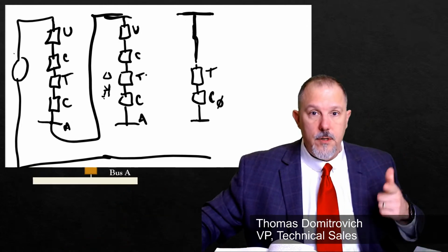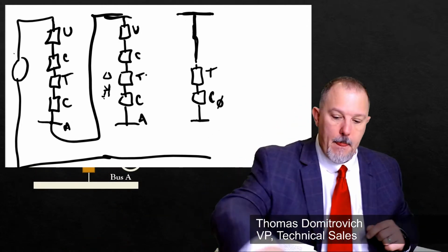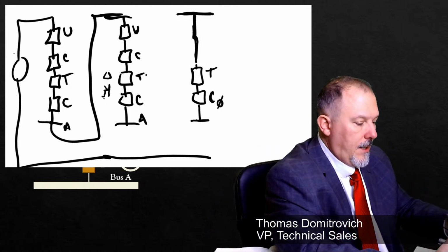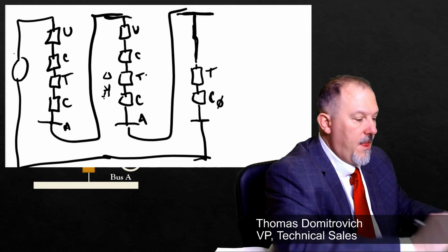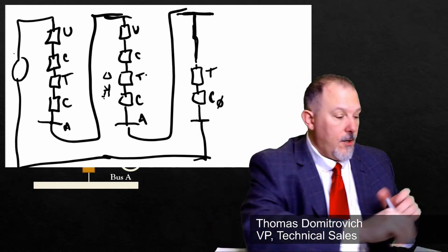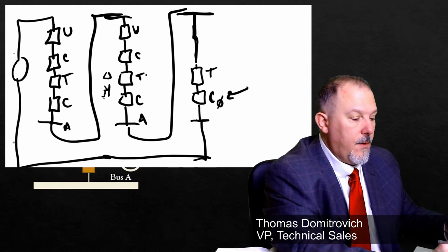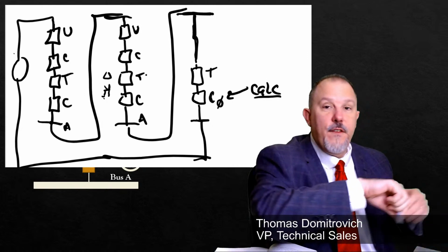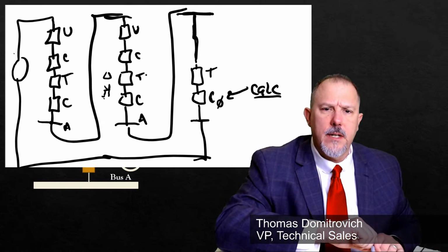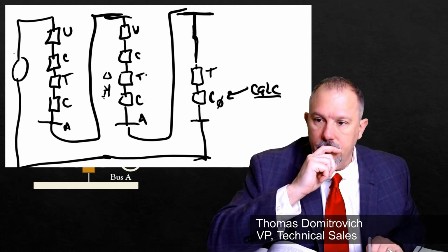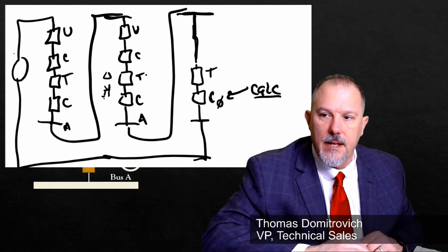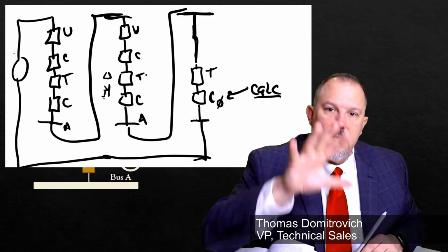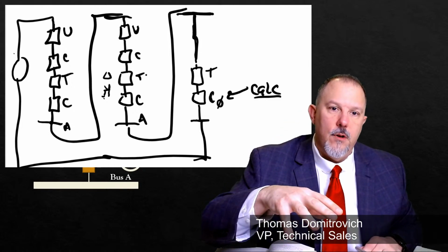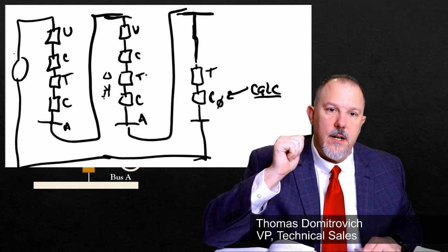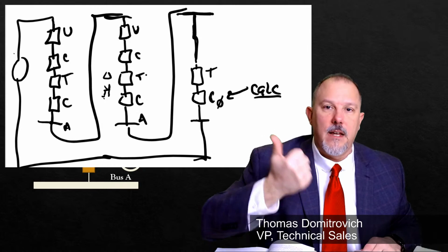So what you would do for this system is, that is your circuit. You've got to calculate the new value for the conductor. That would be conductor 2 in our impedance diagram. All right, Robert from Omaha, thank you, sir. Thanks for tuning in. So your equivalent impedance diagram for this ground fault current is going to look like this.